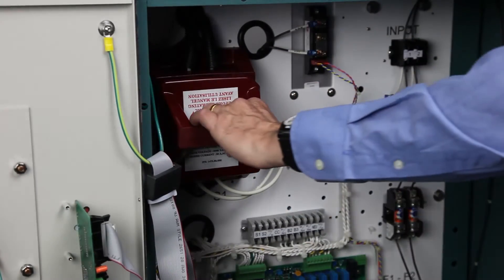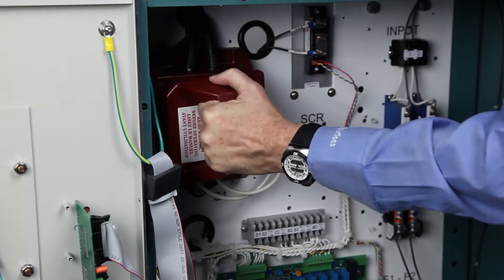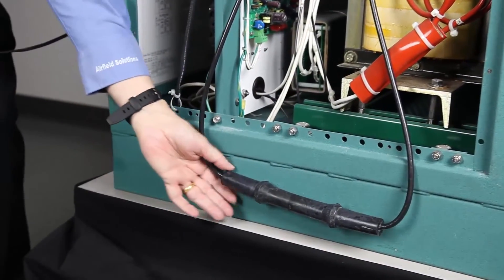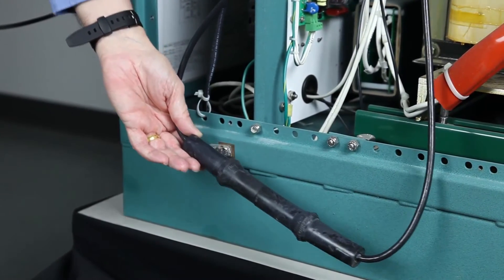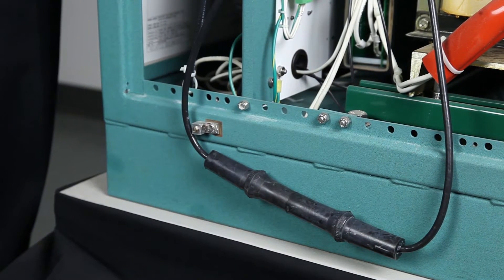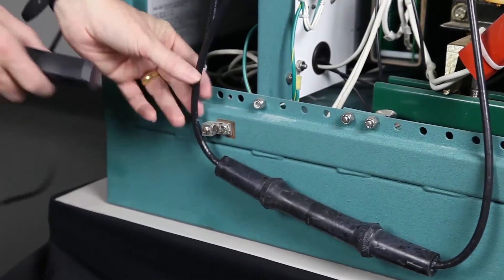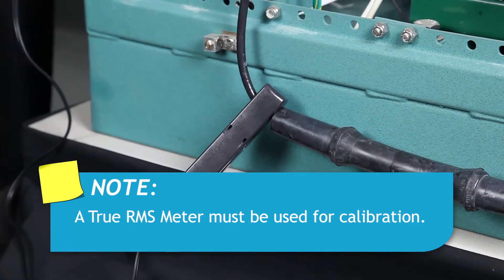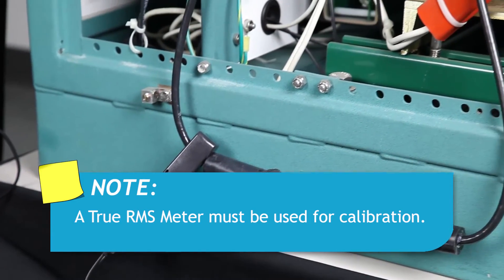Calibrate the CCR with no load present by shorting the regulator's output. This can be done using an SCR or S1 cutout to short the output. It can also be done by placing a short length of series circuit cable across the output. This will avoid the possibility of outputting a higher than normal current into the airfield lighting circuit. Next, attach a true RMS meter with current clamp around the series circuit wire. Since the output current of the regulator will not be a true sine wave, a true RMS meter must be used.